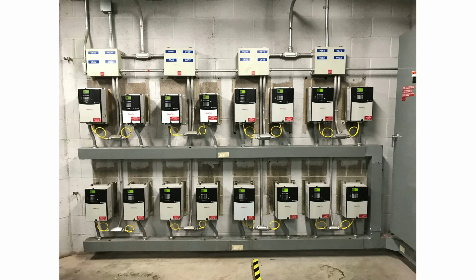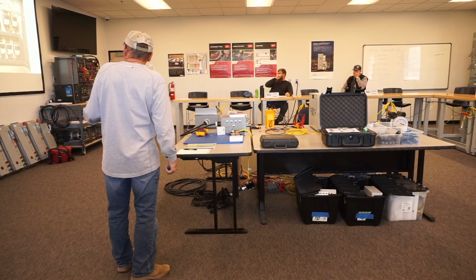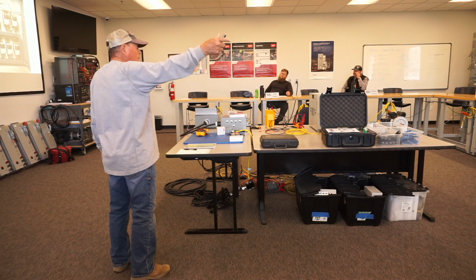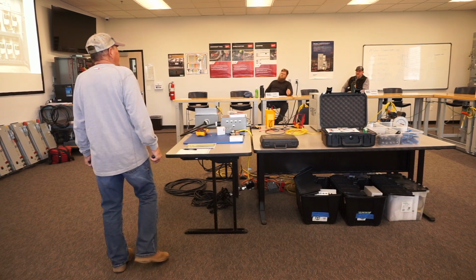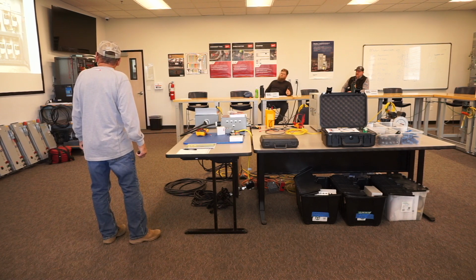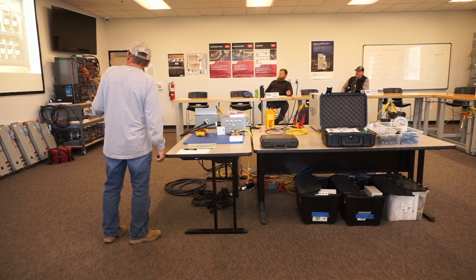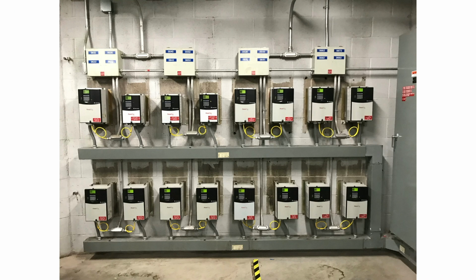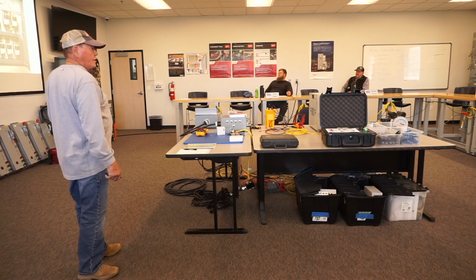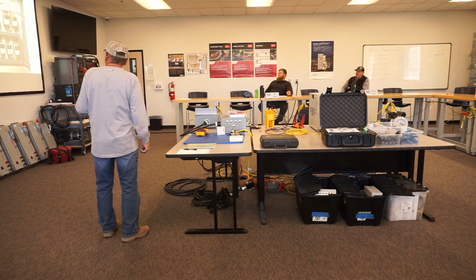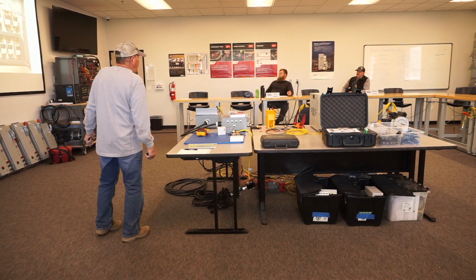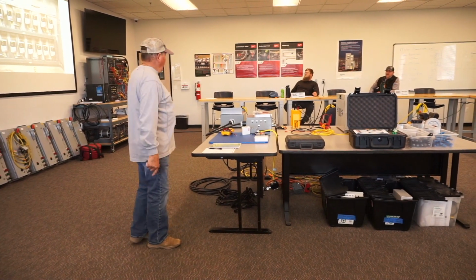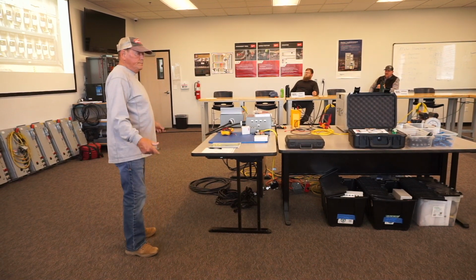the magnetic field around that 10,000 hertz is going to influence the 60 hertz, and the whole thing is just going to, can't work. And it's just like a heater. And to travel that far, and your motor's 400 and 500 feet away, and you're using building wire, what are we going to do? I said, well, based on what I'm seeing here, you had an electrical contractor, I'm assuming, put these new drives in. I says, whoever he was, I said, you probably better take him out in the desert and bury him. Because his electrical contractor should not install drives like that. I said, you're gonna have to re-pipe all of this and pull VFD wire out to those motors and put filtering on to correct the problem.